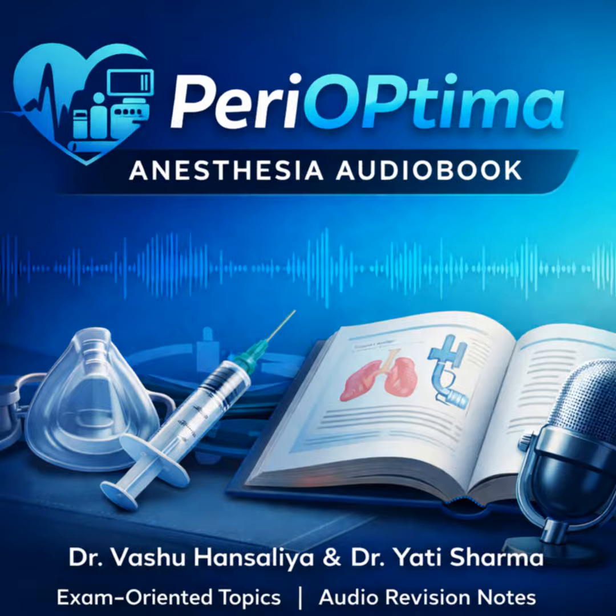But it's extremely inefficient for controlled ventilation. Terribly inefficient. When you squeeze the bag, the positive pressure pushes the fresh gas that's near the bag out of the APL valve near the patient. The CO2-rich gas near the patient just stays in the reservoir tubing, waiting to be rebreathed. So the FGF requirement for controlled is very high.